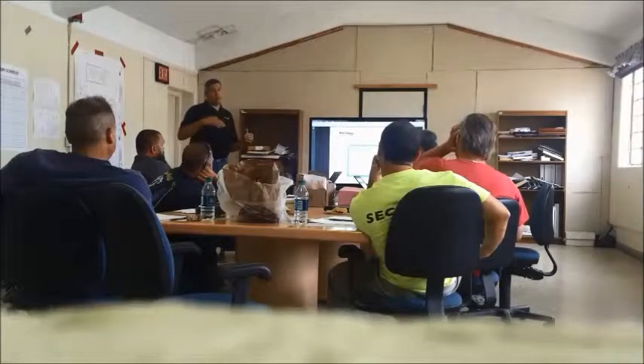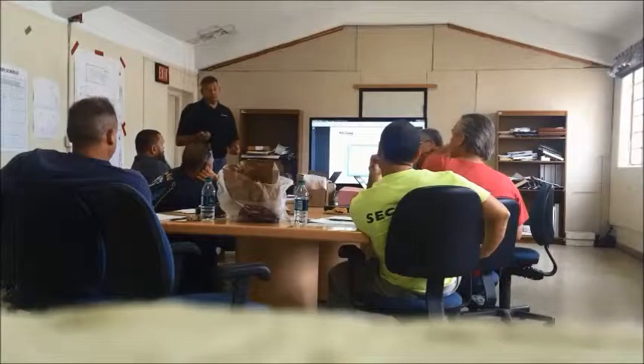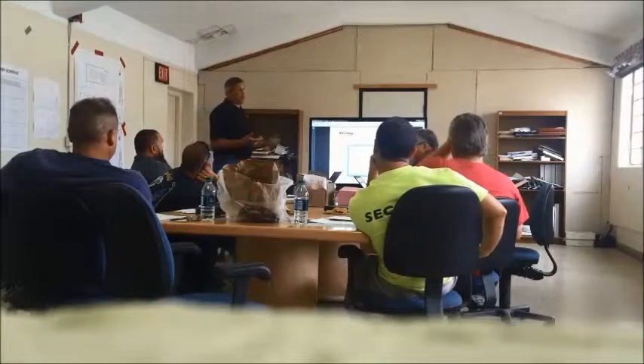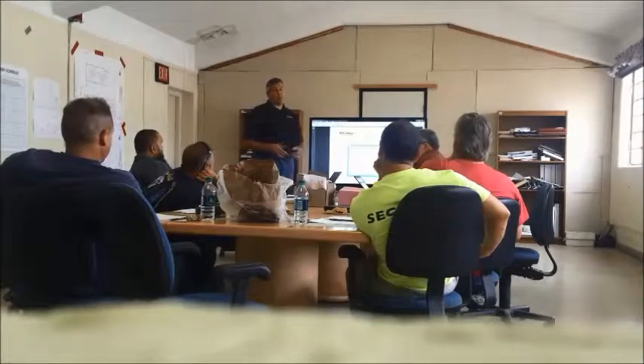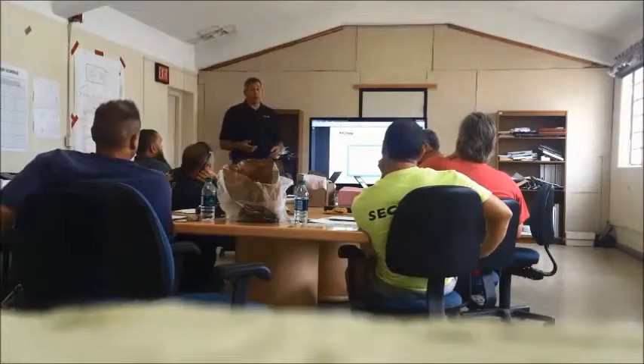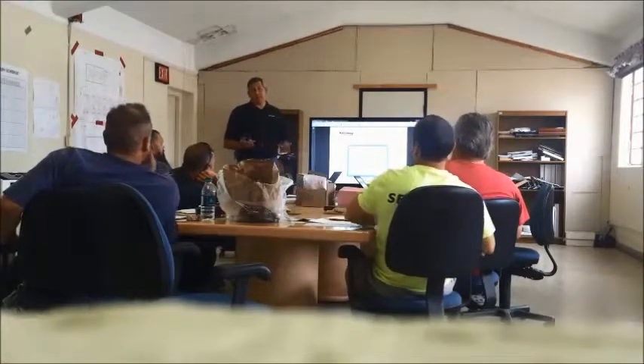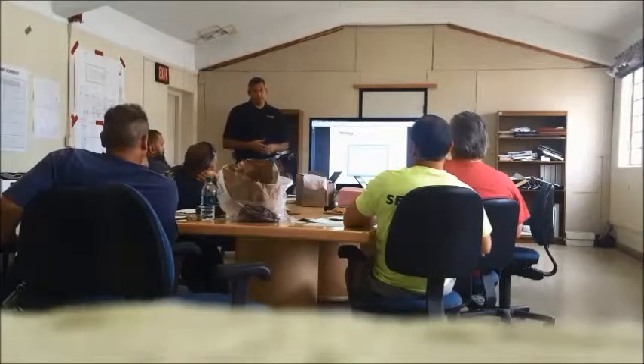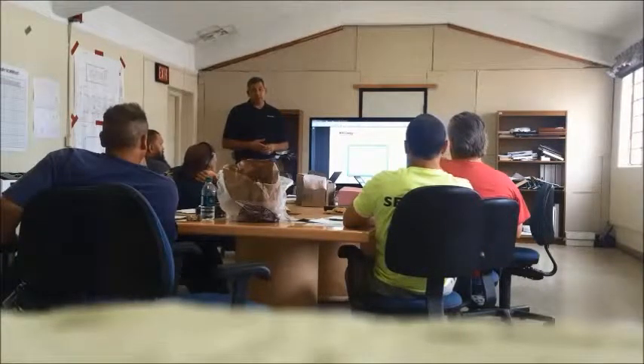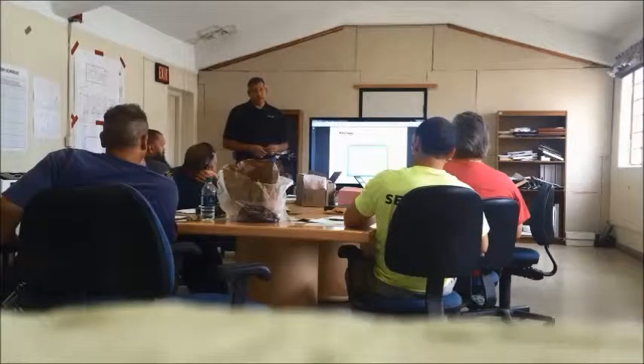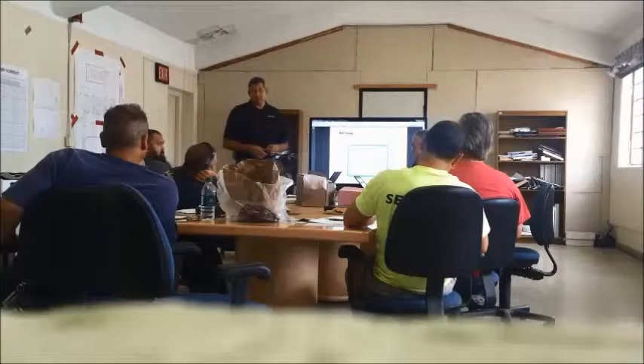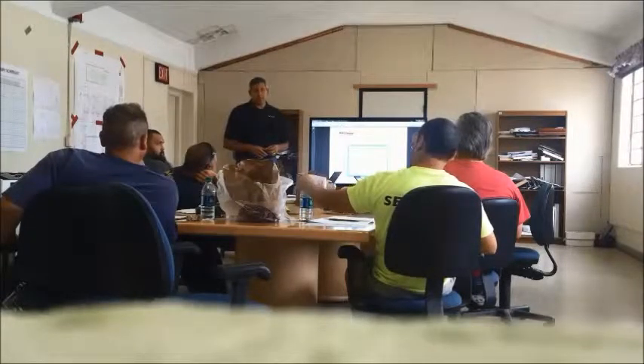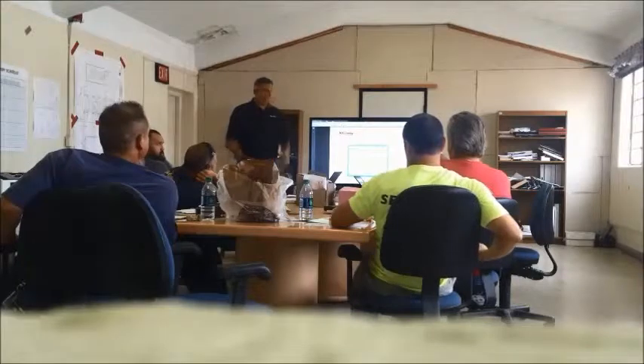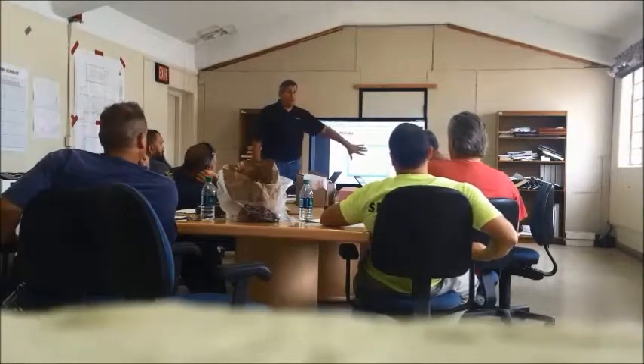And they were talking about maybe adjusting it higher based on the door pulls, but it's at 0.6. So if you walk up to the panel and it says it's in fire life safety mode, it allows the exhaust to continue to run. However, it allows us to have egress, or that allows someone to get out of the building safe. Okay. You don't want to change that wiring or change that logic. So the exhaust has to have a module, and this is a fire system. This is the control panel that runs the entire exhaust system. That's standalone on a panel.